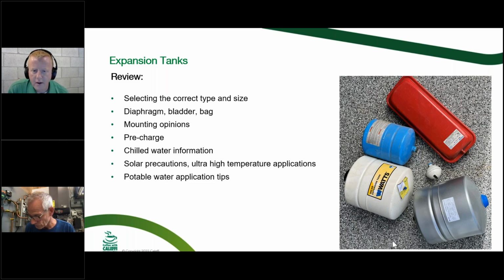Yeah, there was one question in here, and I think this is a great one. Is there any downside of using a potable tank for hydronic systems rather than a hydronic specific tank? And I think the big thing there is, one, the potable is going to be a lined tank, so you don't have access directly to the steel inside those tanks. The other big one is that the pre-charge is going to be a lot higher in a potable tank versus a hydronic tank, so make sure you're checking on that. The other big difference is the connection size, usually 1/2 inch versus 3/4.